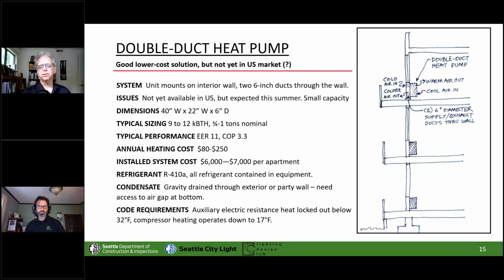One last thing before we move on. This and many of these other heat pumps are requiring that the auxiliary electric resistance heat is locked out above 32 degrees. Once you get below freezing, you can start using some electric resistance, but the compressor doesn't just turn off and turn the thing into a toaster oven. The compressor keeps working down to well below what Seattle design temperatures are, and that's in the code.